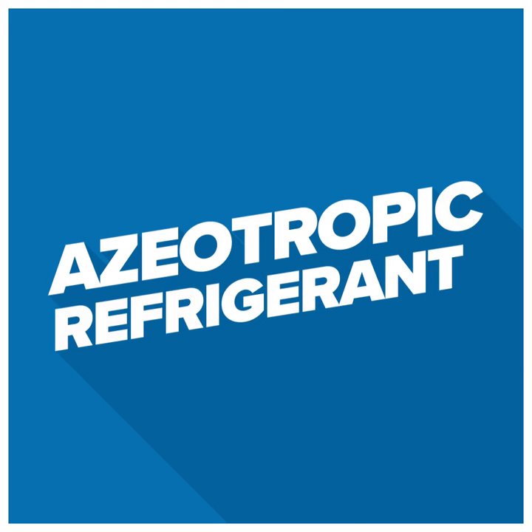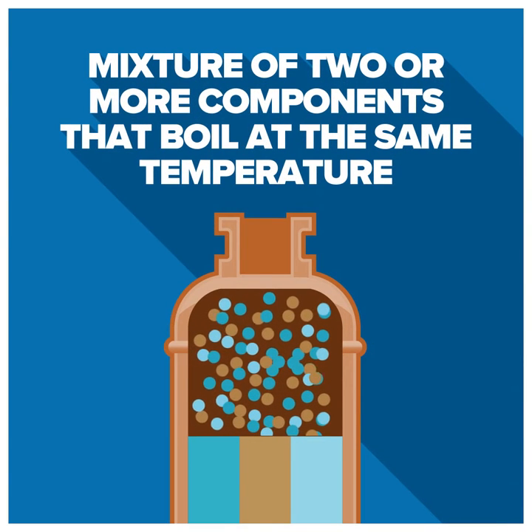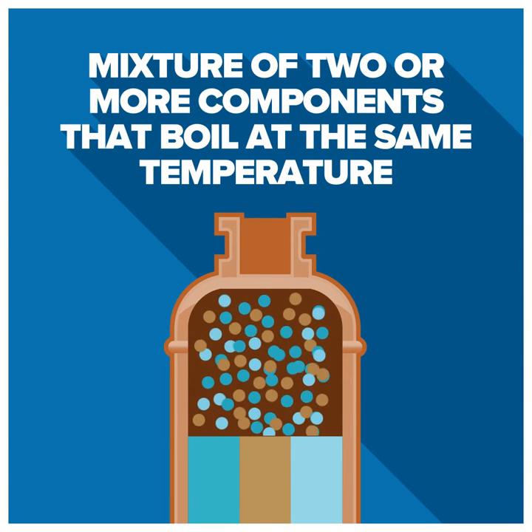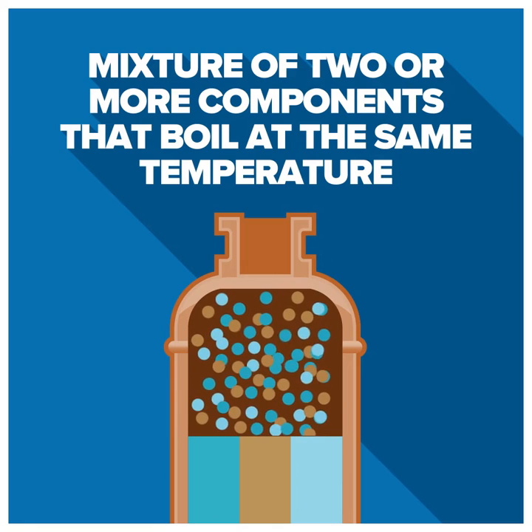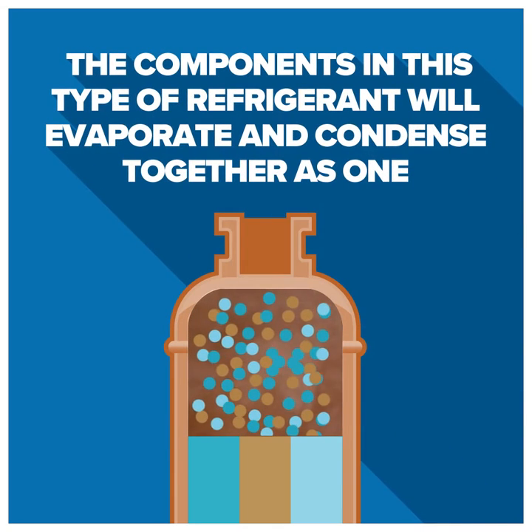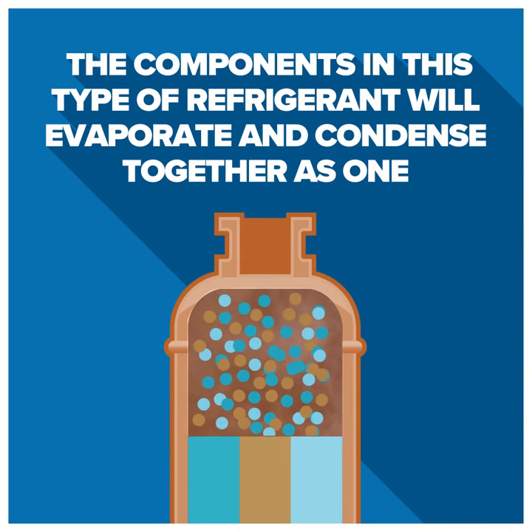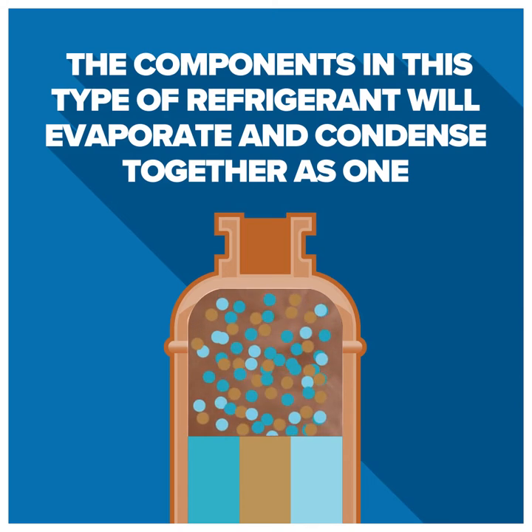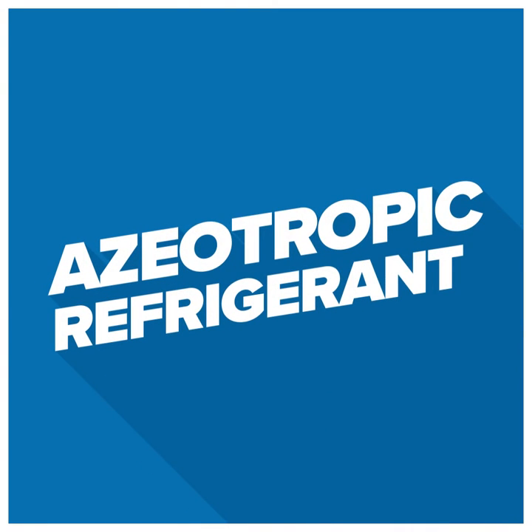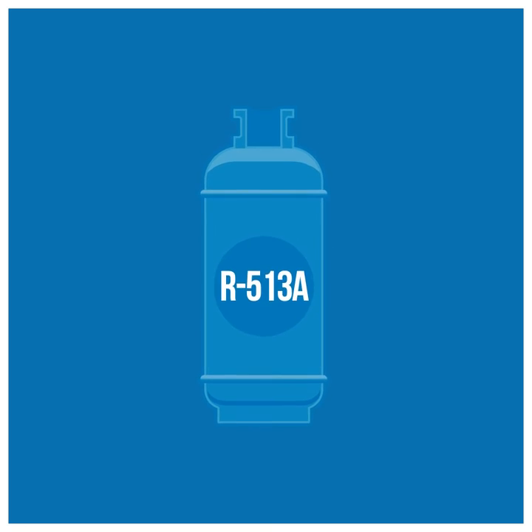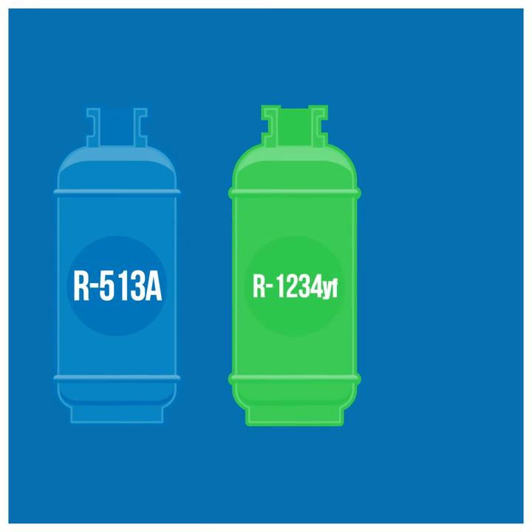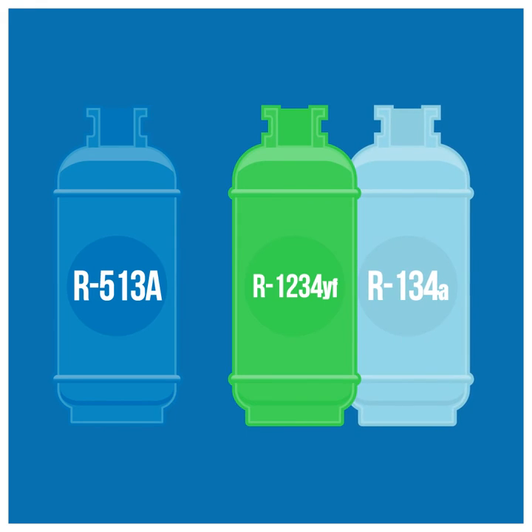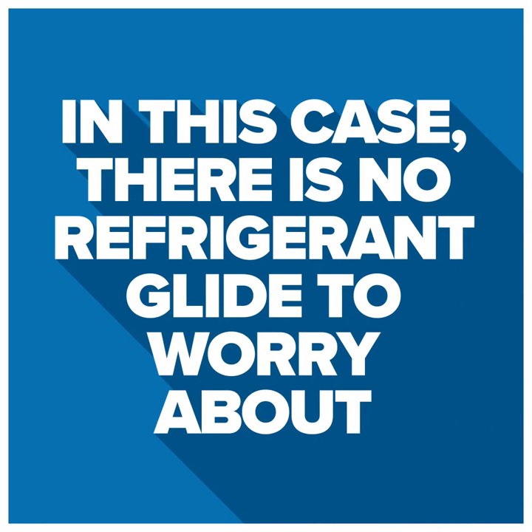An azeotropic refrigerant is a mixture of two or more components that boil at the same temperature. The components in this type of refrigerant will evaporate and condense together as one. An example of an azeotropic refrigerant is R513A, which is a blend of R1234YF and R134A. In this case, there is no refrigerant glide to worry about.